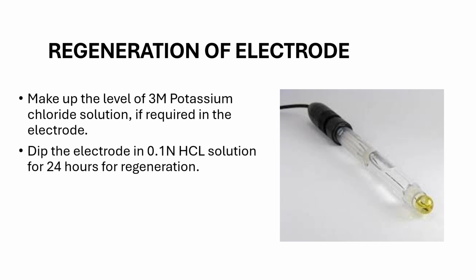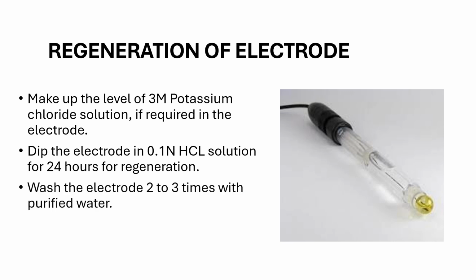Next, dip the electrode in a 0.1 normal HCl solution for 24 hours. This step helps to regenerate or activate the sensing membrane, restoring the electrode responsiveness, right? After 24 hours, remove the electrode from the HCl solution and rinse it 2 to 3 times with purified water. This ensures that any residual acid is removed before calibration. Now that the electrode has been regenerated, proceed with calibrating the pH meter to confirm it meets the required accuracy, as we already discussed the procedure of calibration, right? With the regeneration process complete, your electrode is now reactivated and ready for accurate pH measurement, right?